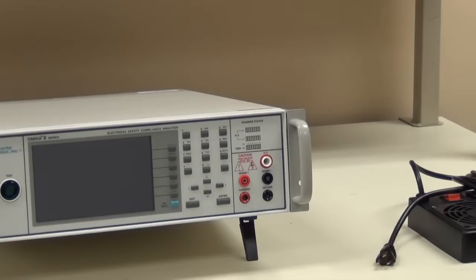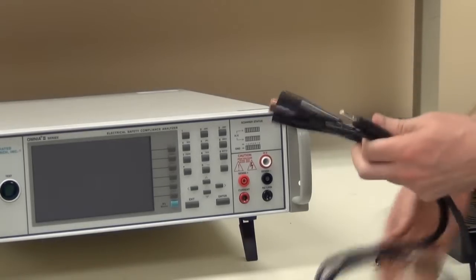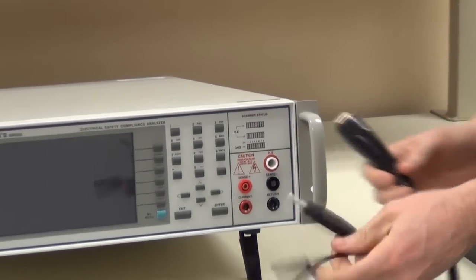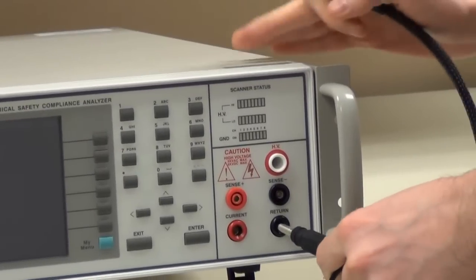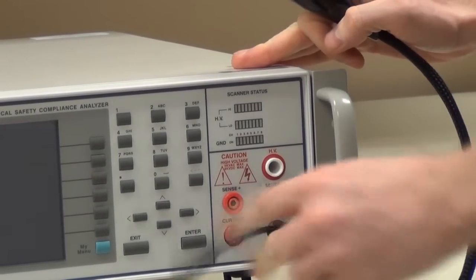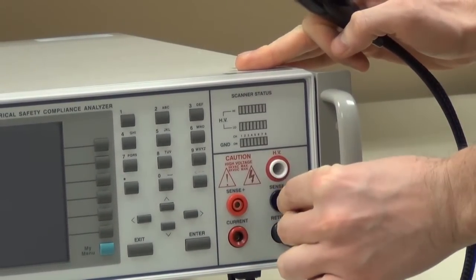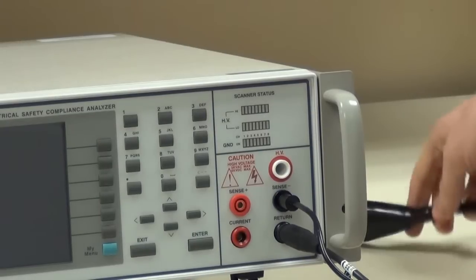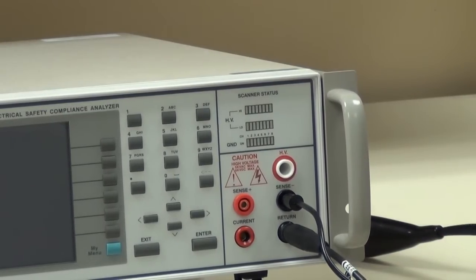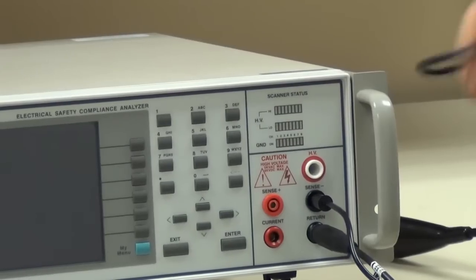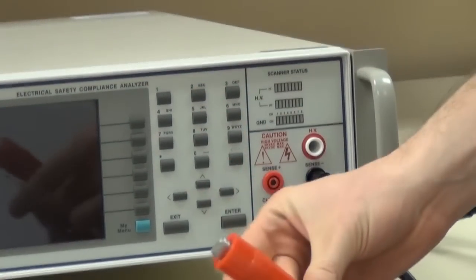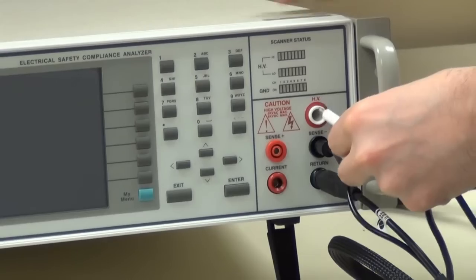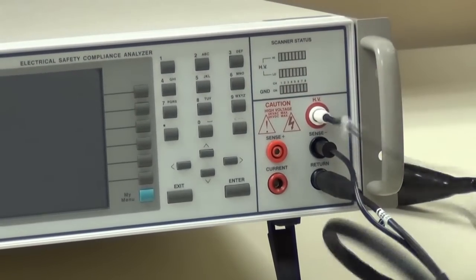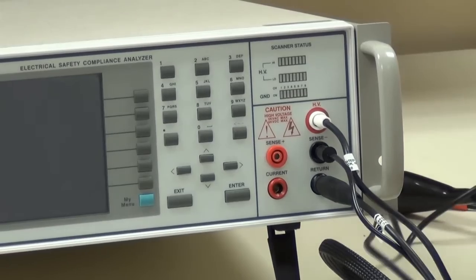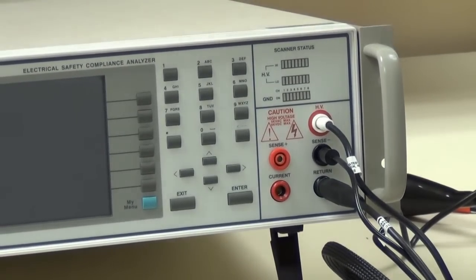Not every product terminates in a 2 or 3 prong line cord. For devices that require a different connection set, test leads may instead be utilized. First, plug the black return lead into the return terminal on the front or rear panel and the black Kelvin lead into the sense minus terminal. Then, connect the high voltage lead, terminated in a red clip, into the HV terminal on the front panel of the instrument. Attach the clip terminated end to the return lead to the case or chassis point of the DUT.